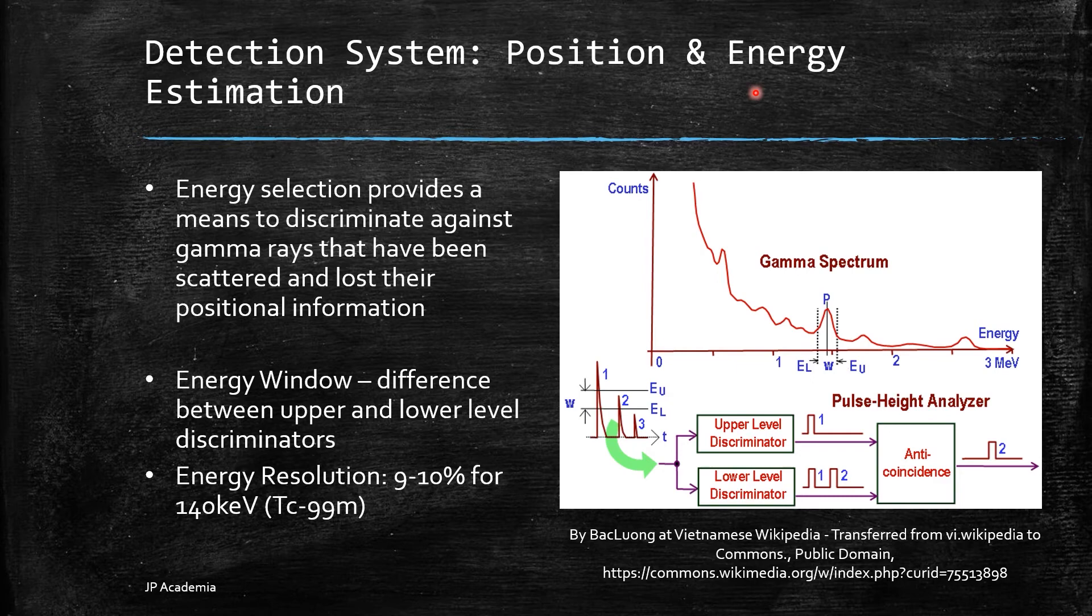Pulse height analyzer principle is described by this picture. We have three pulses. Pulse 1, pulse 2, and pulse 3 are detected at different times of T. Two discriminators emit a counting signal if their set voltage level is reached by a pulse. Pulse 2 triggers the lower level E sub L, but not the upper level E sub U.